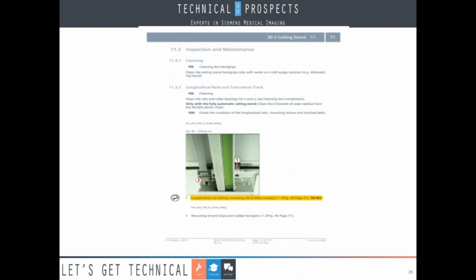Up here is a picture of those rails. The heavy assemblies slide on them and are bolted to the ceiling, torqued to only 50 newton meters, but you should check them every 2 years. I've definitely found some bolts not torqued at 50 newton meters - I don't know what happens, they just become a little loose. Fortunately there are enough bolts that if one's not good you can still torque them every PM. I wouldn't let it go.